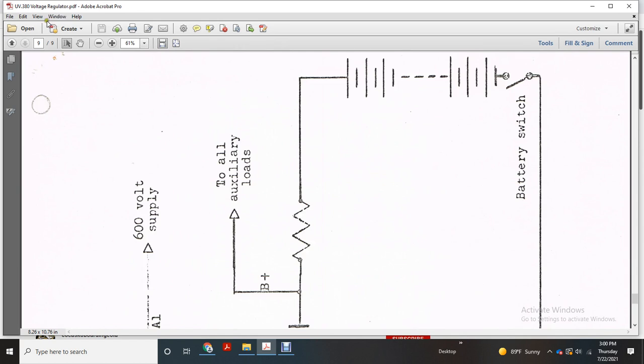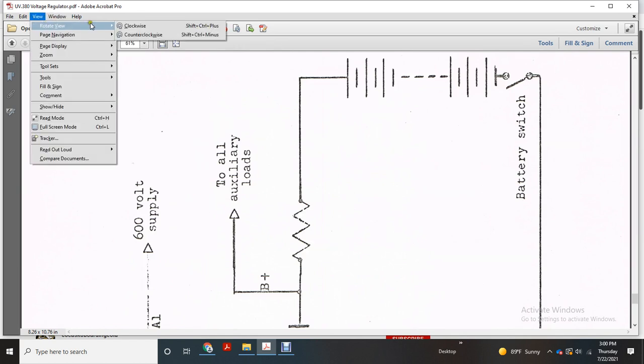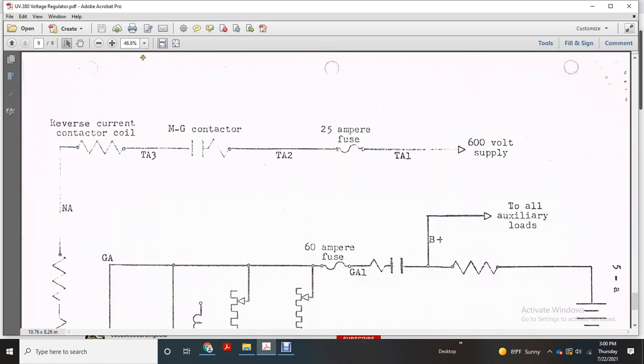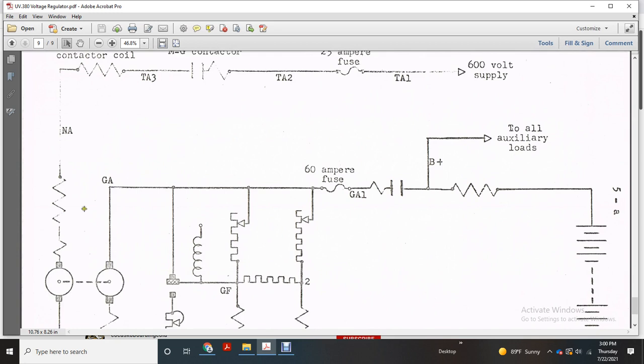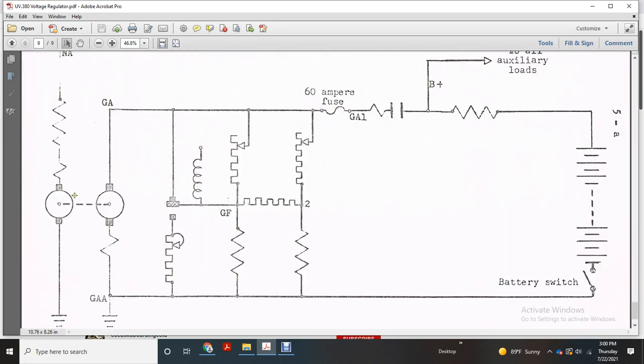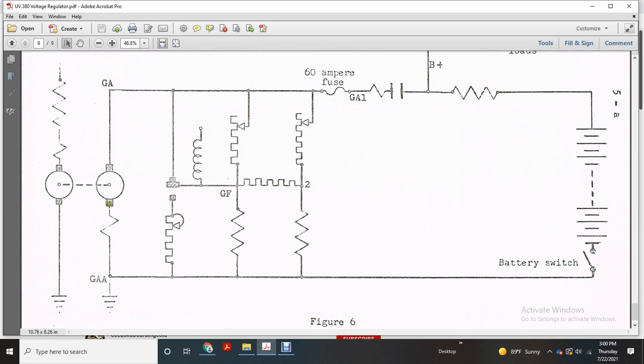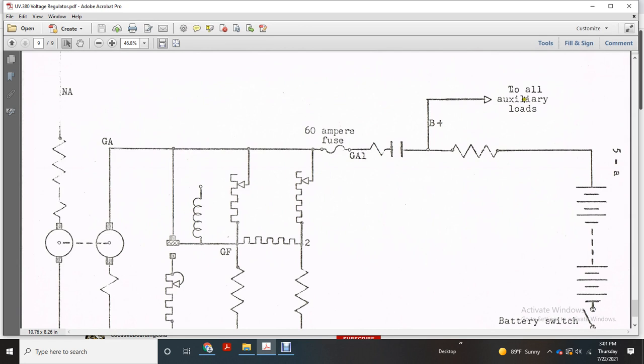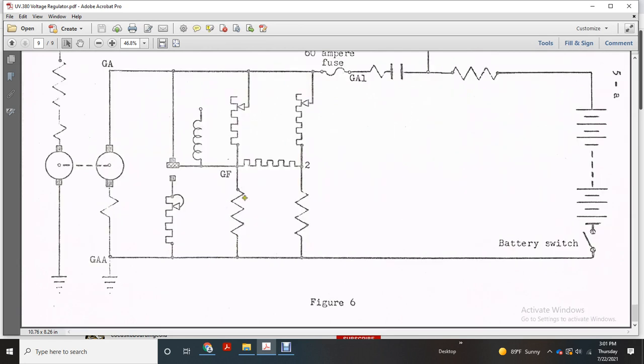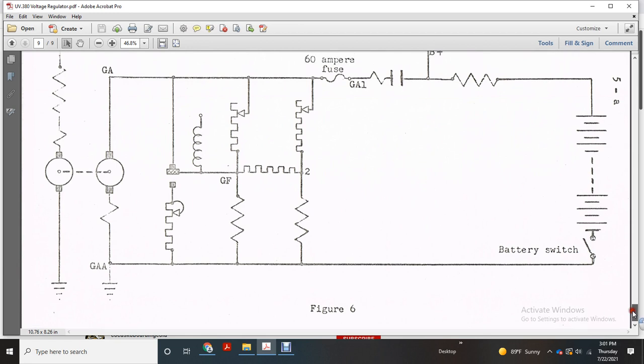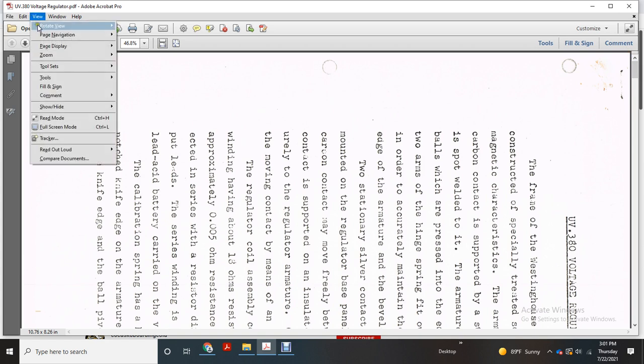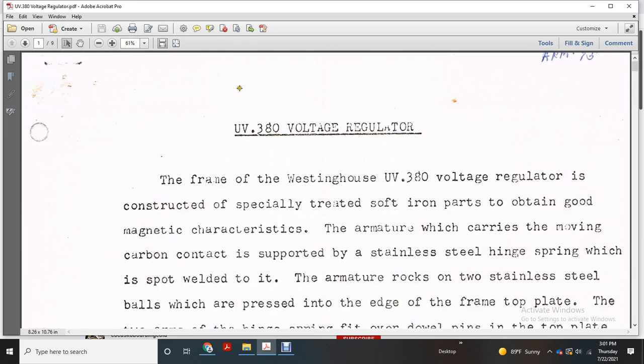And then we'll go over it once more. You have the reverse current contactor coil, magnetic MG contactor, 25 ampere fuse, 600 volt supply, main generator, motor and generator armature, and then a 60 ampere fuse total to all auxiliary loads, battery switch, and you had your series and your shunt, and your number 2 would be your hunting. And then this completes the reading of the UV380 voltage regulator.